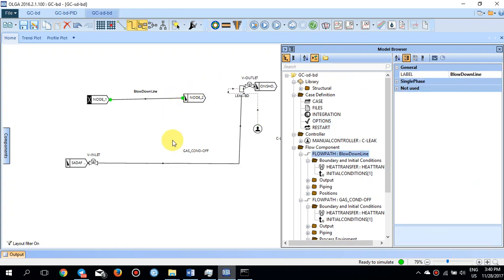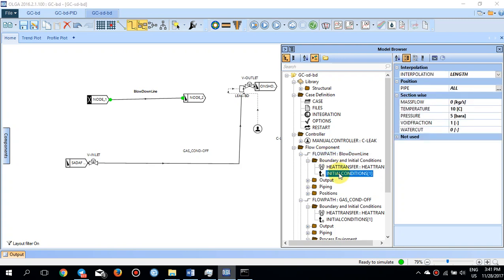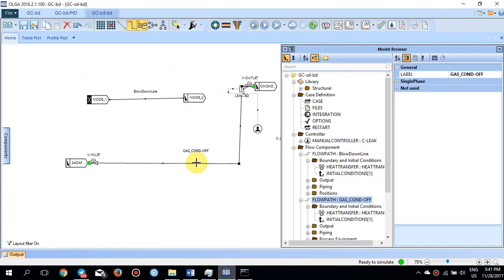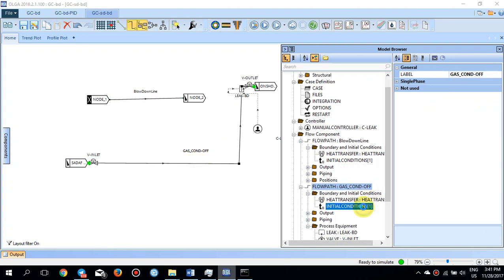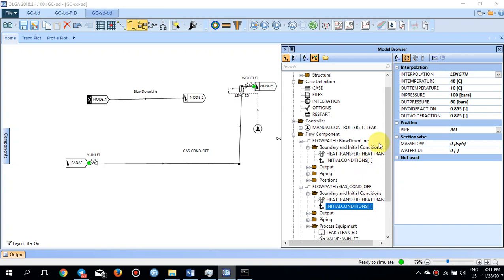I need to define initial conditions for both lines. For the blowdown line, the initial conditions are five bar, void fraction of one, and mass flow of zero. For the gas condensate line, I have defined inlet temperature of 48, outlet temperature of 10, inlet pressure of 100, outlet pressure of 60, with void fractions of 85% at the inlet and 87% at the outlet. I then start running this shutdown scenario.